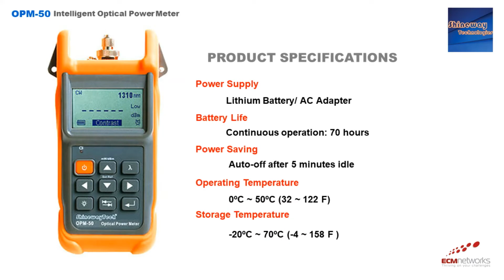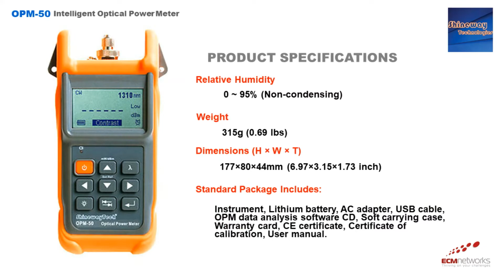OPM50 has a lithium battery which can be used for 70 hours and can be charged using an AC adapter. It also has an auto-off function which will turn off the unit after 5 minutes. Operating temperature is 0 to 50 degrees centigrade, and the storage temperature is -20 to 70 degrees centigrade. OPM50 operates at a relative humidity of 0 to 95% non-condensing. It weighs around 315 grams. It has dimensions of 177 mm by 80 mm by 44 mm.